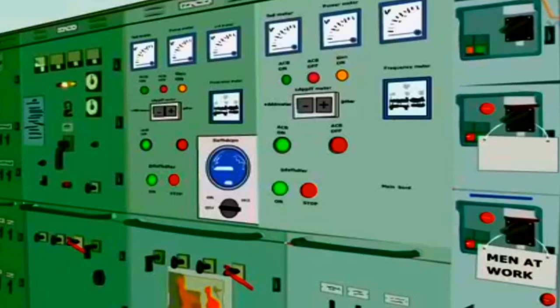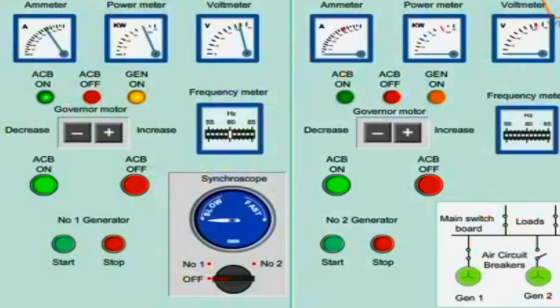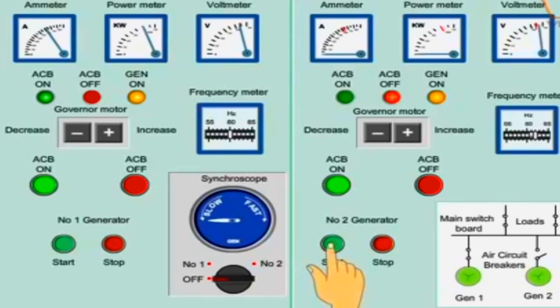The control panel of a generator is located in the main switchboard. Assume that number one generator is running on load. Number two generator needs to be started and synchronized with generator one. Start the number two generator and check the voltage.